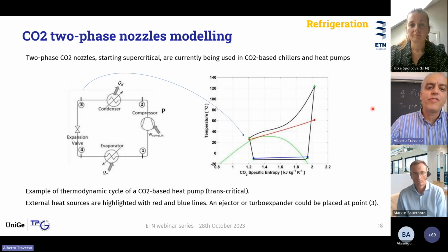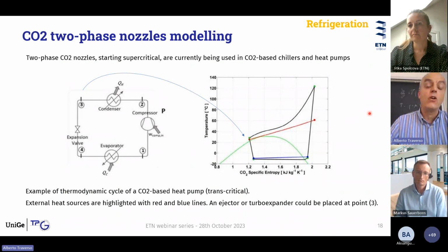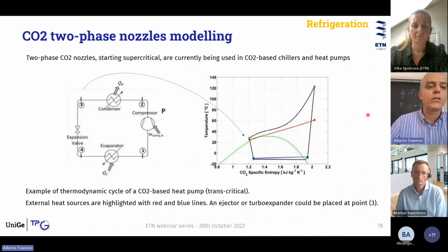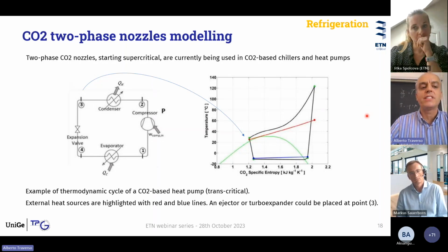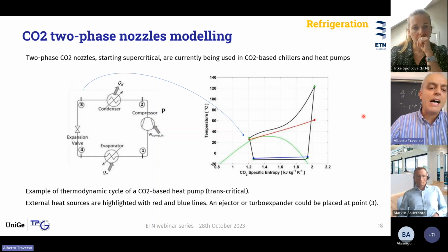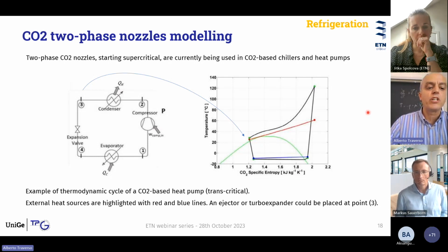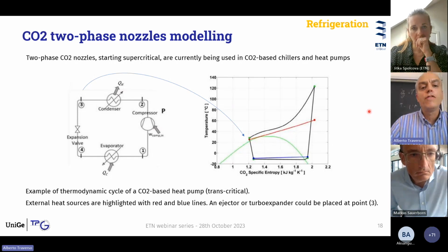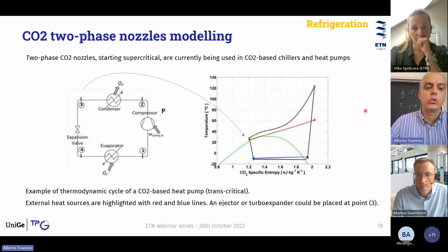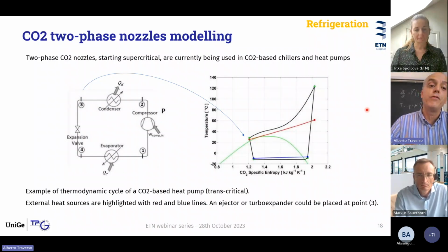Finally, just to provide some food for thought, I'd like to touch on the only present commercial application of supercritical CO2. Supercritical, or better to say transcritical, CO2 cycles are currently used in CO2 refrigeration cycles, especially for large users such as supermarkets or malls. And in this case, we can see that, for instance, in point 3 of this cycle, which is where the expansion occurs in the inverse cycle, there can be two cases commercially. One is just a simple expansion valve. The second one has a nozzle for ejectors. Ejectors are currently used in CO2 refrigeration cycles. One third option, which could be a future market perspective, is to use an expander in point 3.